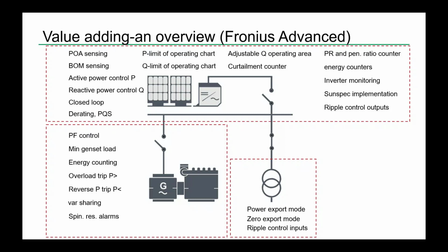But if you look at the engine/generator in the box on the lower left side, you can see we have power factor control and minimum genset load. All of this is controlled by adjusting the PV inverter. Of course, counters, we had the overload and reverse power trip that I mentioned before, load sharing, and your spinning reserve alarms. And for the utility incomer or utility feeder, you have power export mode, zero power export mode. This is available, and of course you can control it with set points directly or from inputs.